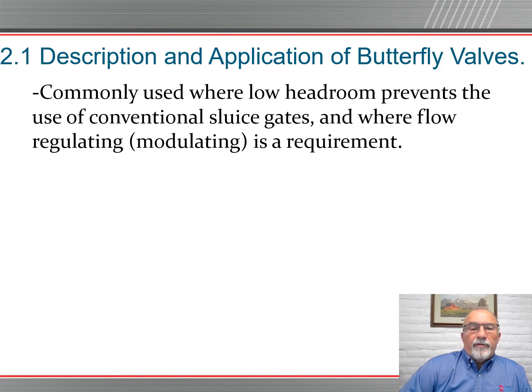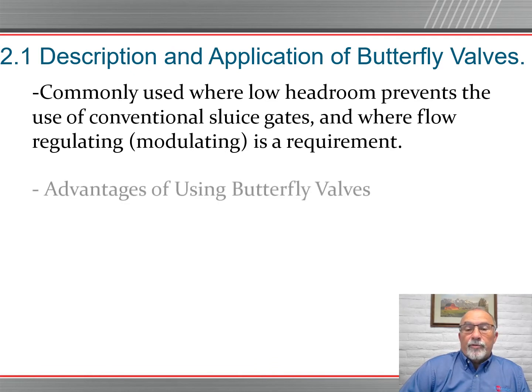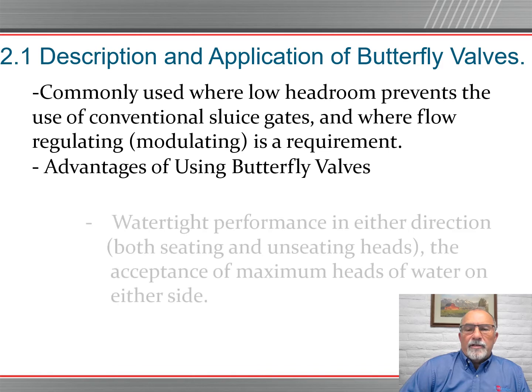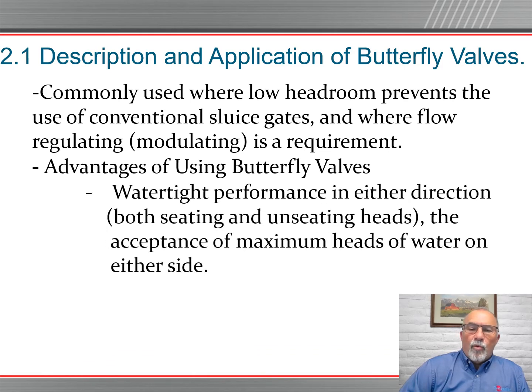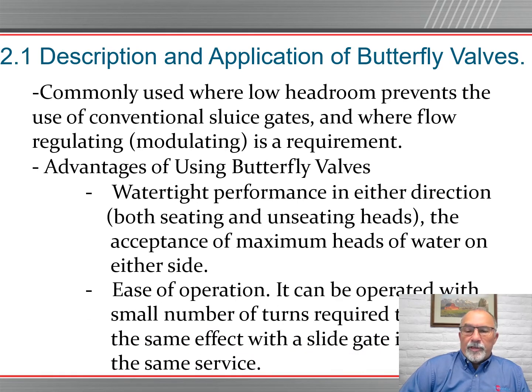Description and application of butterfly valves. Commonly used where low headroom prevents the use of conventional sluice or slide gates, where flow regulating or modulating is a requirement as well. Advantages of using butterfly valves: there are watertight performance in either direction, both seating and unseating heads, the acceptance of maximum heads of water on either side. They can be operated with small number of turns required to achieve the same effect with a slide gate in the same service.